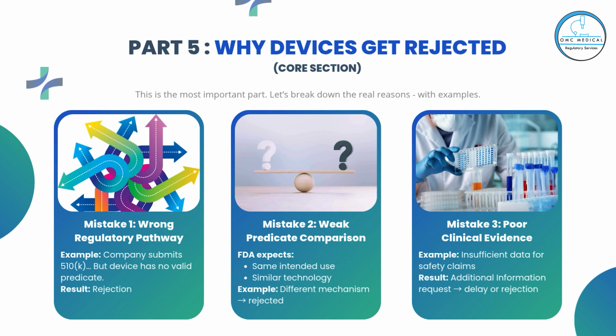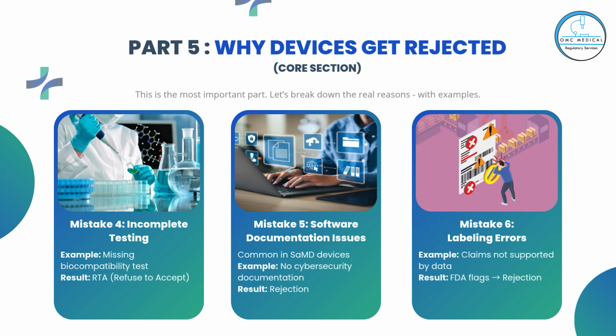Mistake 1. Wrong regulatory pathway. Example: company submits 510K, but device has no valid predicate. Result: rejection. Mistake 2. Weak predicate comparison. FDA expects same intended use, similar technology. Example: different mechanism leads to rejection. Mistake 3. Poor clinical evidence. Example: insufficient data for safety claims. Result: additional information request leads to delay or rejection. Mistake 4. Incomplete testing. Example: missing biocompatibility test. Result: RTA, refuse to accept.